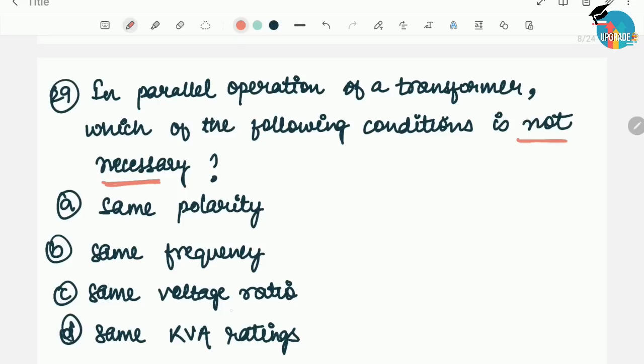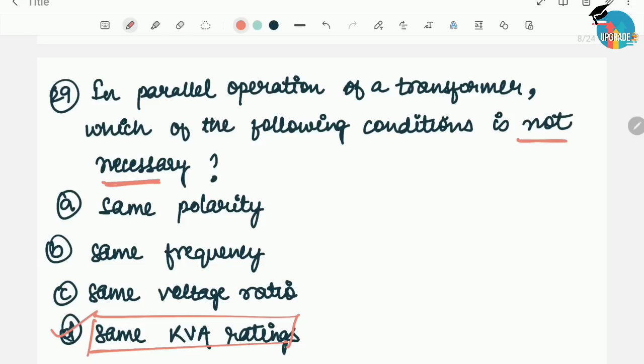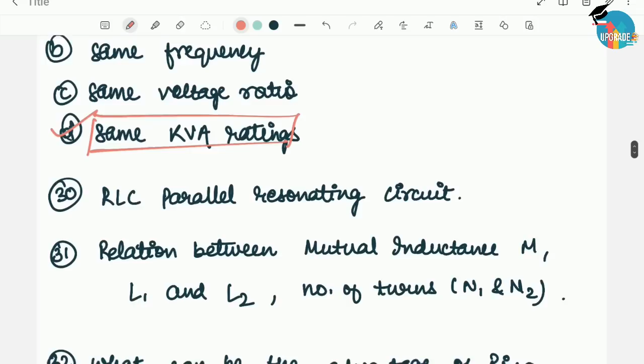The necessary conditions for parallel operation of transformers are the same polarity, same frequency, and same voltage ratio. The not necessary condition is the same kVA rating, since both transformers can have different kVA ratings and still operate in parallel.